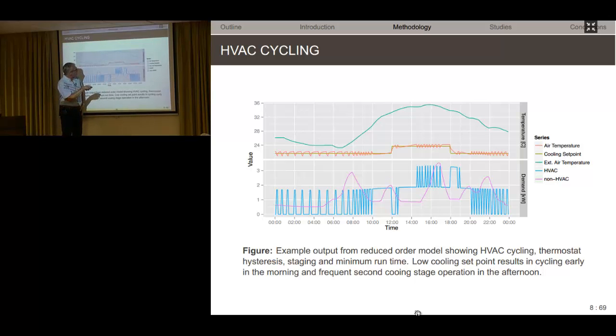And then there is a period in the afternoon around 6 p.m. where we have both stages running continuously. What would that be? What happened there? It's 6 p.m. It's no longer the hottest time of the day. It's only 32. Exactly. So the set point is being reduced, and so I'm actually asking my system to work very hard at that point of the day. I'm going to stick with this for now.